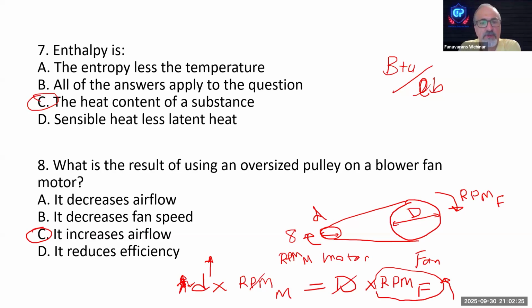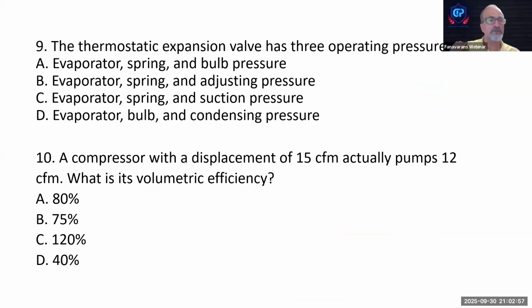So if you had 700 RPM before and you change to a larger pulley, this 700 goes up to, for example, 900. When the speed of the fan goes up, the airflow goes up. That's a fan law. We talk about air distribution a lot in the fan laws. So C is the right answer. Question number 9.